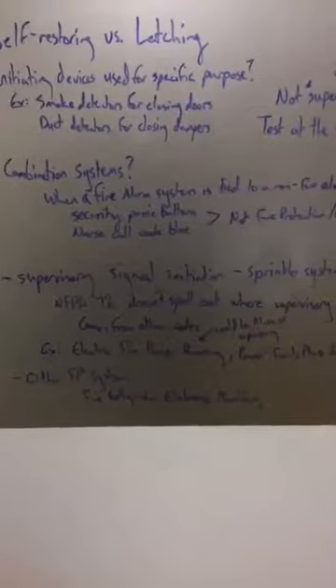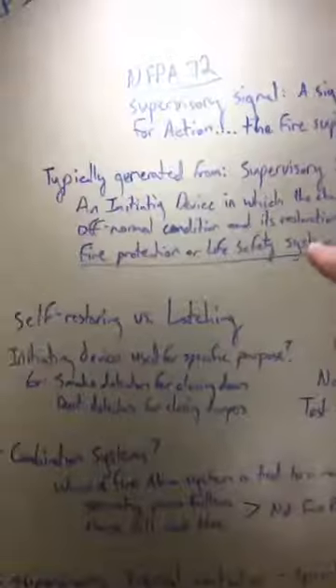phase reversal. You'll also see some that do generator running, knowing that your fire pump's running on alternate power. Again, those aren't necessarily required. So you've got to go to the right code to figure out if they're supposed to be there or not. But if they are there because it's a fire protection or life safety system, then it has to be tested quarterly.